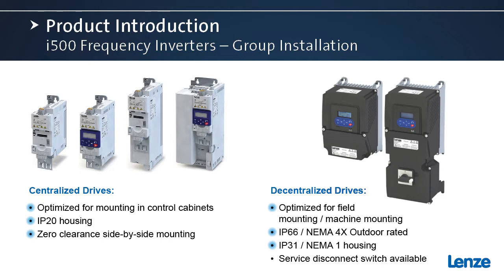With the IP66 NEMA 4X housing, there is also an optional service disconnect switch available. That switch is really intended for servicing the motor and the equipment directly driven by the motor that's connected to the frequency inverter.